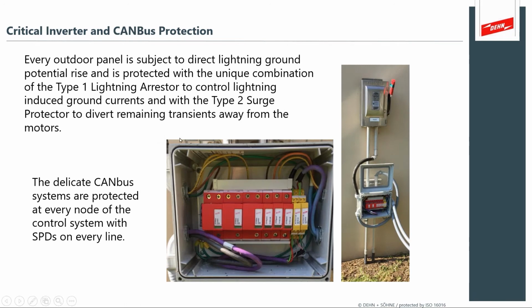This is a typical photograph of what you might see distributed around the power generation plant, near pumps, near the areas that are very highly exposed around the plant. And you'll see the recommendations for both type 1 and type 2 surge protection devices. Now, these are IEC type 1, which are rated to withstand the high ground potential rise that you'll see at these extensive power generation facilities.